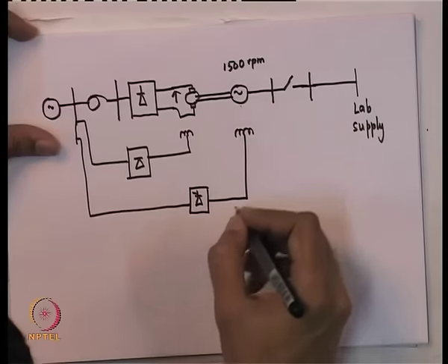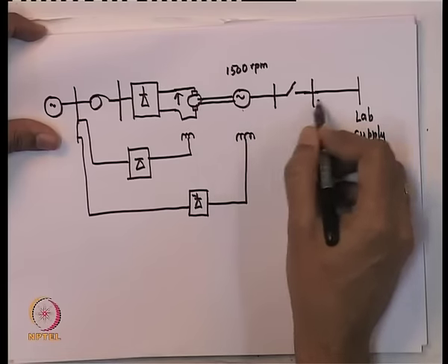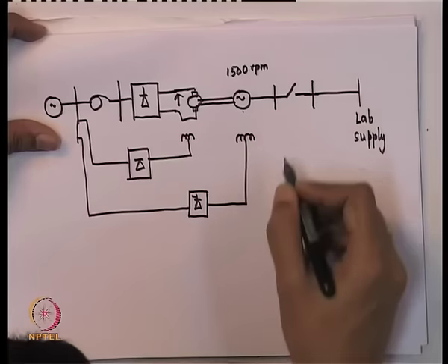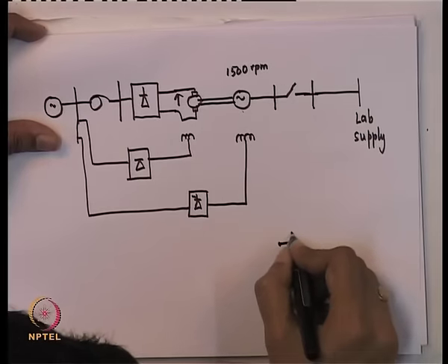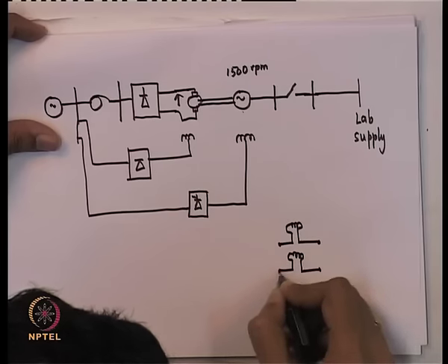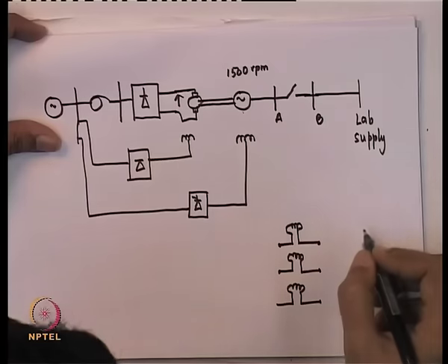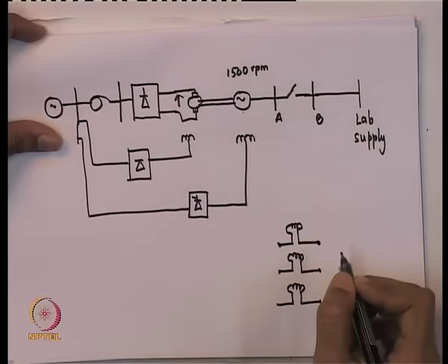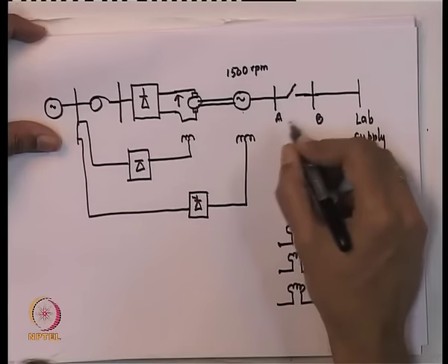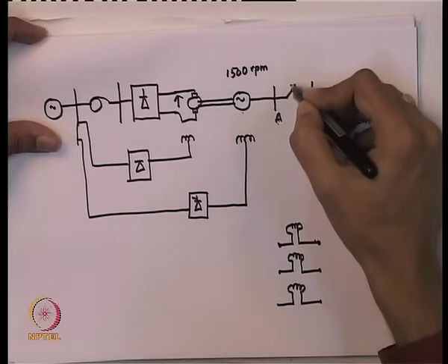Now, how do you ensure that before you connect, the voltages and the voltage phases in each phase are almost the same? You do it by measuring the voltage across both points, or one simple way of doing it is you connect some high resistance bulbs in each phase. So, if you have got point A and B, in parallel with this switch, you connect a bulb. If this bulb is always dark, absolutely dark, it would mean that the voltage across A and B is zero all the time. Okay? And in that case, it is a good time to switch on this.